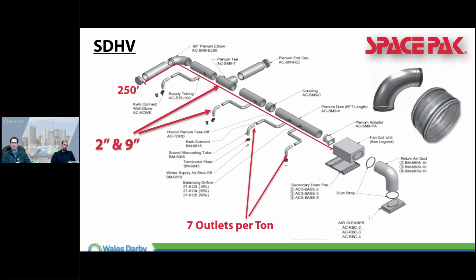So can we do it? Absolutely, it's just a matter of doing it correctly. And just to throw it out there, we say 9, that's the pipe, and then we have the insulation, so call it 12 actual without pipe, without compromising the R value. Same thing with the 2 - the 2 is really 4, somewhere around there, without crushing it.